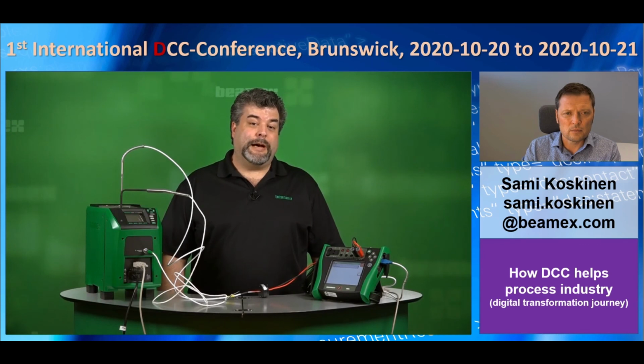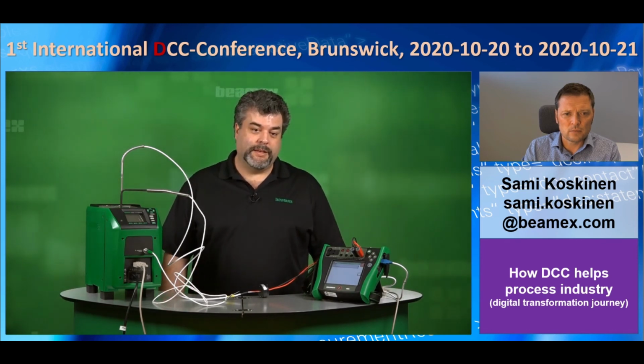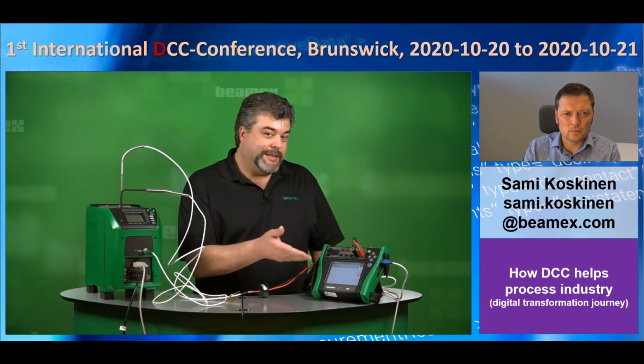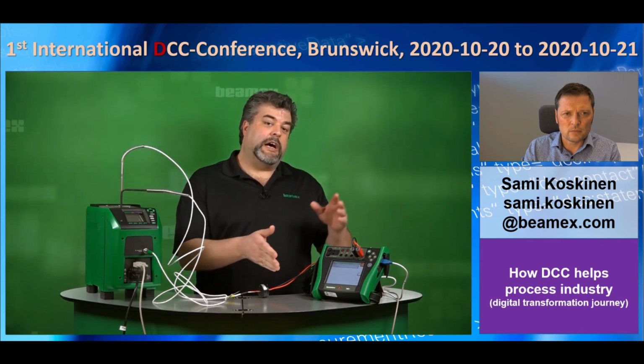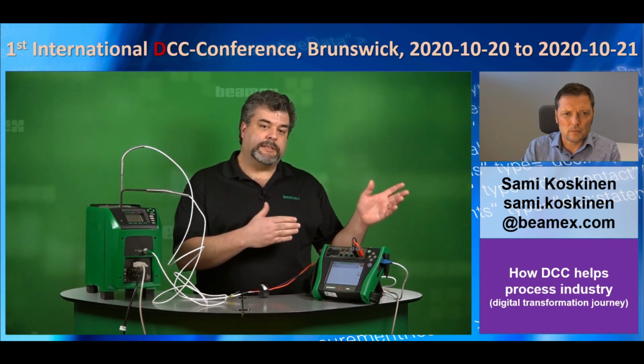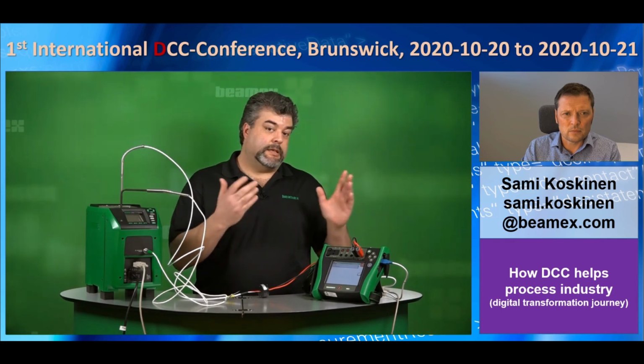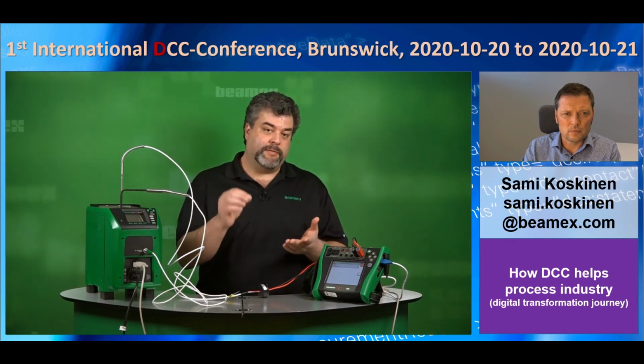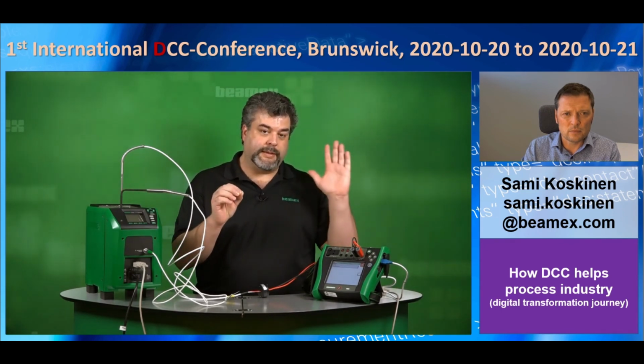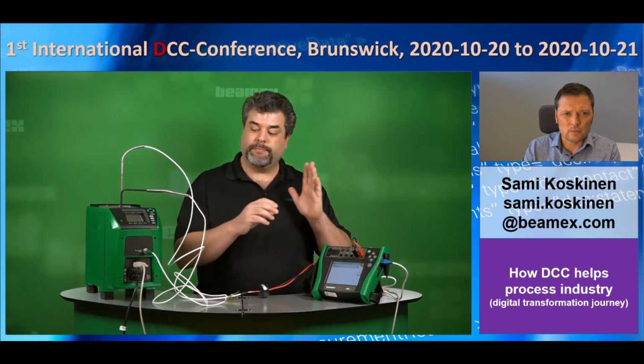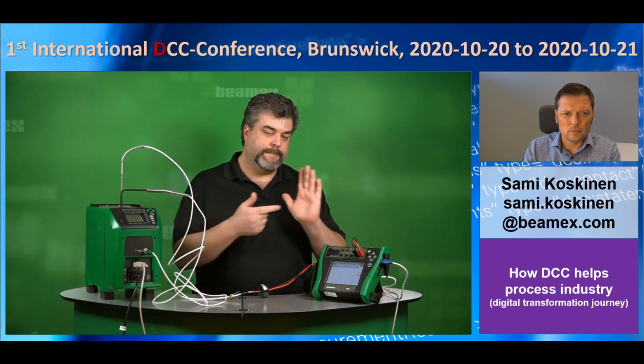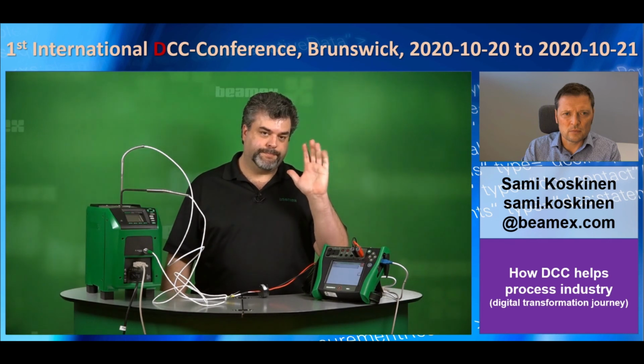So now you know how to do an automatic calibration of a temperature loop using an MC6 calibrator and an FB150 temperature block. In this case, our next step would be to take these results and unload them into our CMX calibration software. Again, through this entire process, we've never picked up a pen or a piece of paper. This is completely paperless automatic calibration with the push of one button.